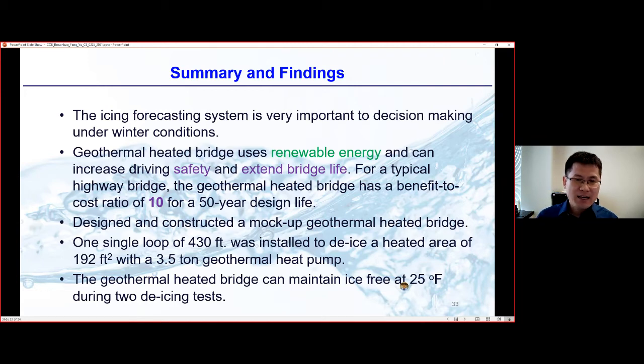If you consider the bridge design life at 50 years, one investment gets you 10 times the benefits back. We designed and constructed this mock-up geothermal heated bridge. The underground loop is 430 feet, the heated area is 192 square feet, and the geothermal heat pump is 3.5 ton.